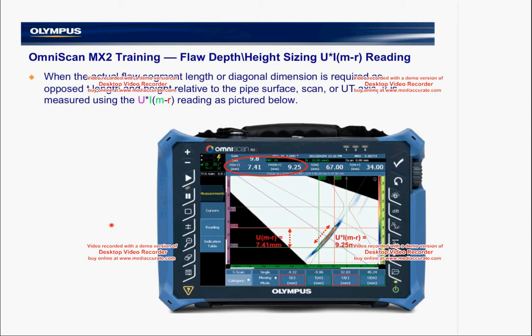When we have to define a segment that doesn't line up vertical or horizontal, such as with the 3D segment tool in TomoView, we have the ability to do this as well. Similarly to all of the previous readings, this reading will define an XY position from the reference cursor on both axes, an XY position from the measure cursor on both axes, and calculate the trigonometry between the two.